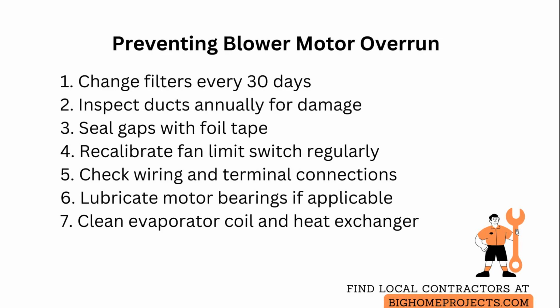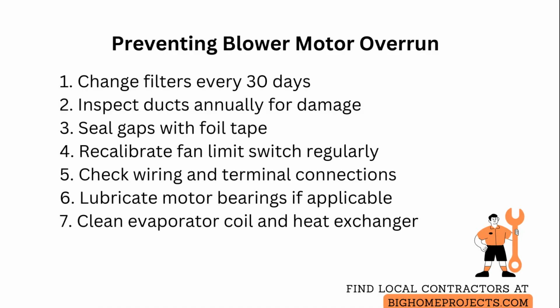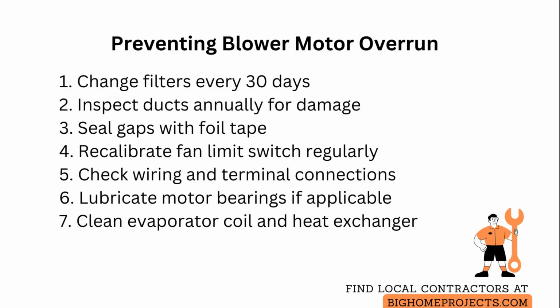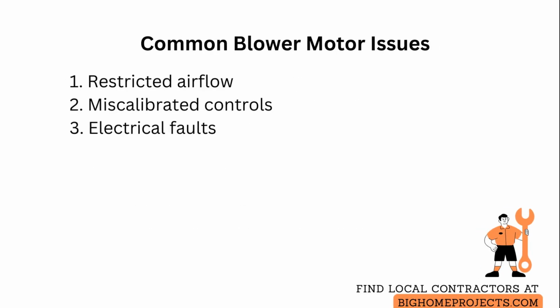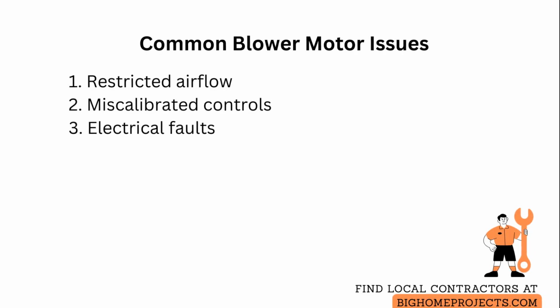Keep the evaporator coil and furnace heat exchanger clean. A restricted coil increases temperature differential and can keep the fan running longer as the system struggles to reach set points. 3 common causes are restricted airflow, miscalibrated controls, and electrical faults, and each has a simple fix.